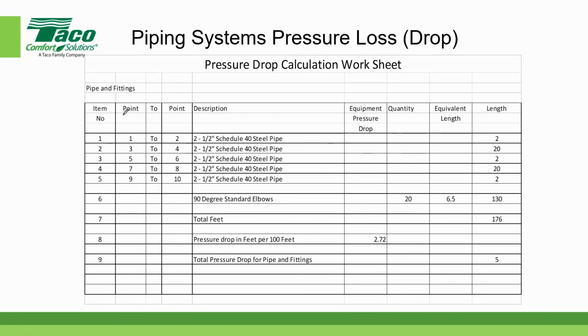So I've labeled this point to point. Point 1 to point 2, under the description, I've told you what it is. It's 2.5-inch schedule 40 steel pipe. And I have several headings: the equipment pressure drop, the quantity, the equivalent length, and then the length. In this case, I just have a straight piece of pipe, so all I have is the length of pipe, and that's 2 feet. And between points 3 and 4 is another section of pipe. In this case, that section is 20 feet. And from 5 to 6, that section of pipe is 2 feet. They're all the same size pipe, 2.5-inch, but they're different lengths.